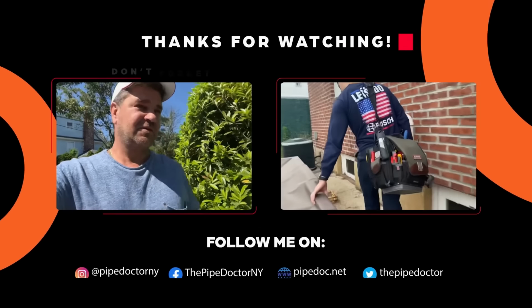That 8211 means the inverter saw excessive line current and started limiting compressor speed. And that can happen for a number of things like low incoming voltage combined with heavy load. So now we have something more specific to investigate and document the next time, instead of saying, well, it runs great, we'll see you next year. And that's why, folks, when you call Pipe Doctor Home Services, you're not just getting us in and out in 10, 15, 20 minutes, half an hour. We perform maintenance. Maintenance isn't just cleaning. It's looking at the history, finding problems before they leave someone without any heating or cooling.